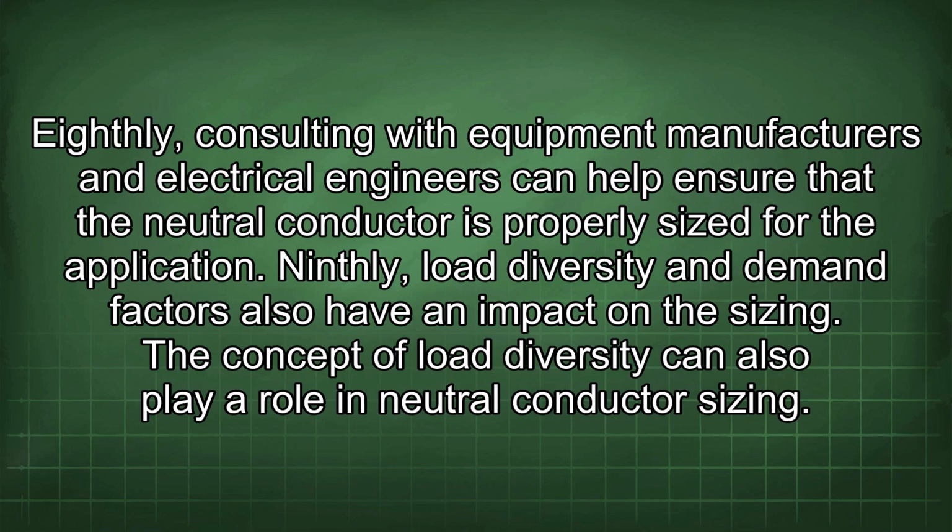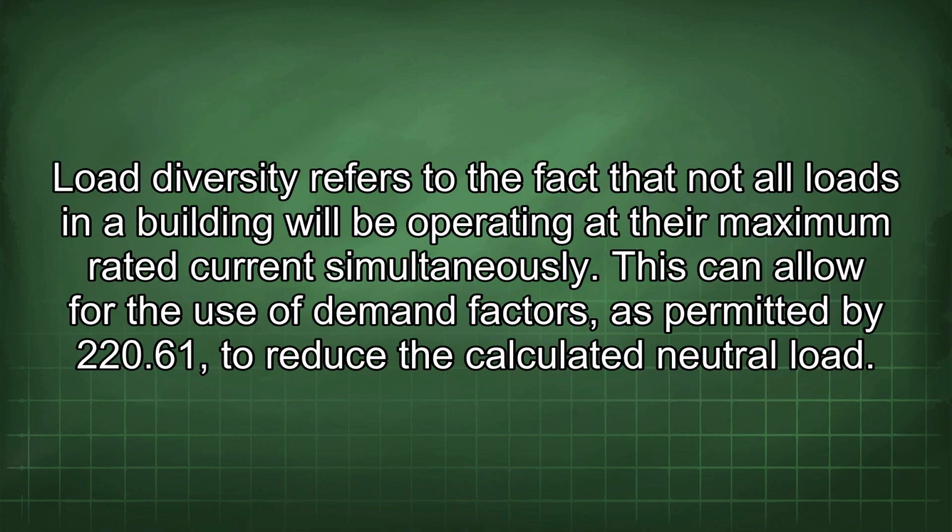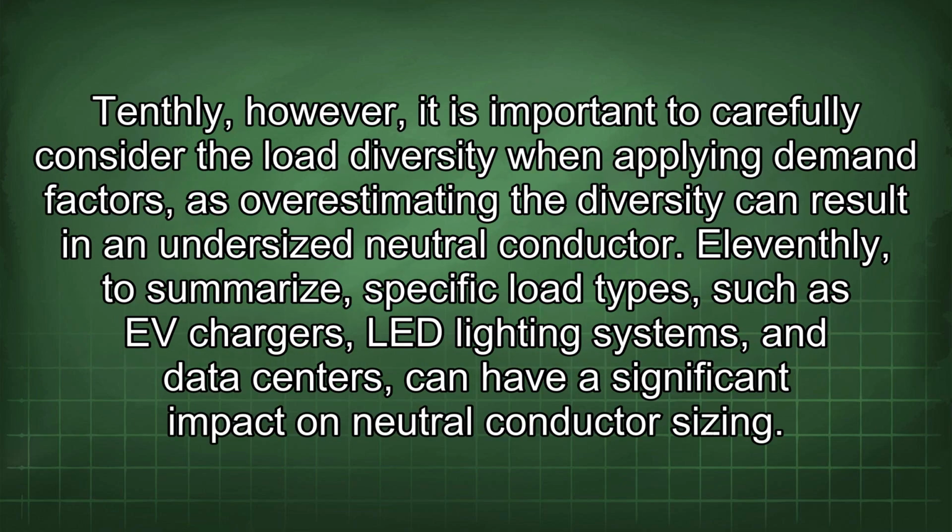The concept of load diversity can also play a role in neutral conductor sizing. Load diversity refers to the fact that not all loads in the building will be operating at their maximum rated current simultaneously. This can allow for the use of demand factors, as permitted by 220.61, to reduce the calculated neutral load. Tenthly, however, it is important to carefully consider the load diversity when applying demand factors, as overestimating the diversity can result in an undersized neutral conductor.